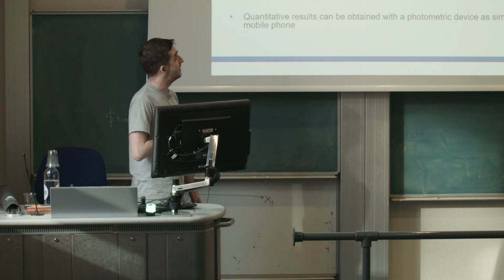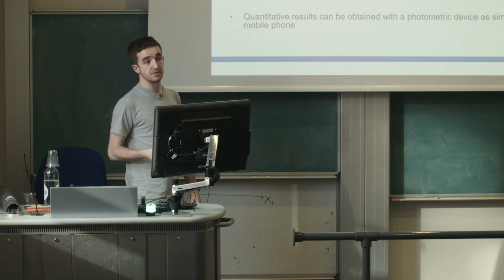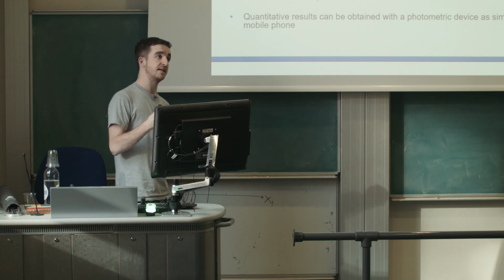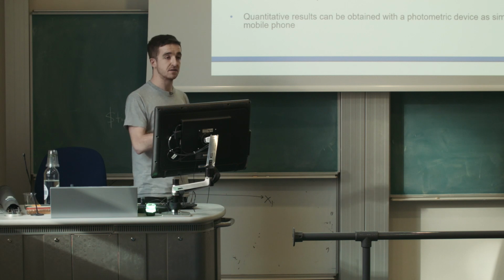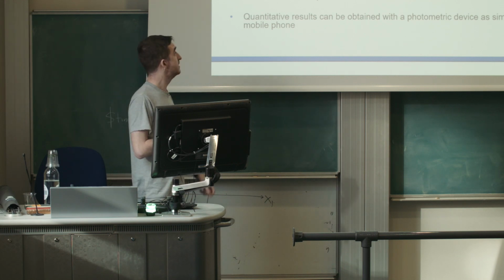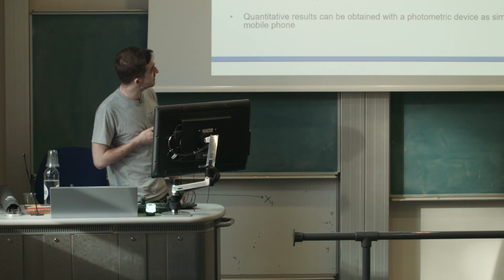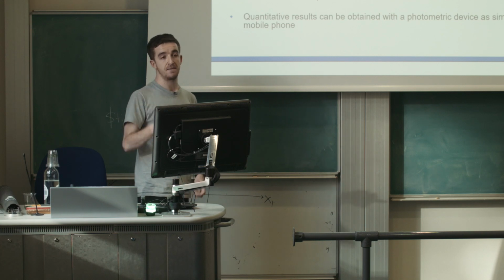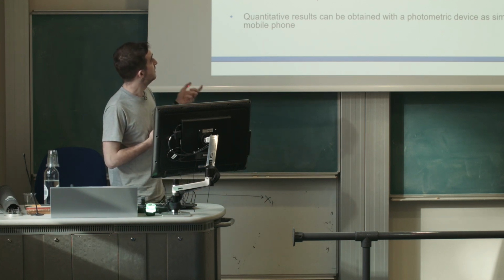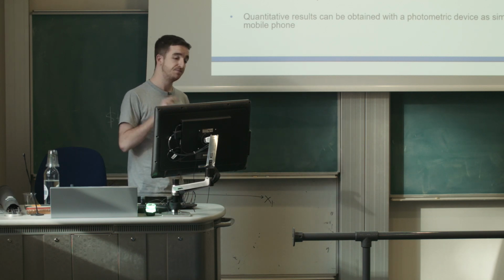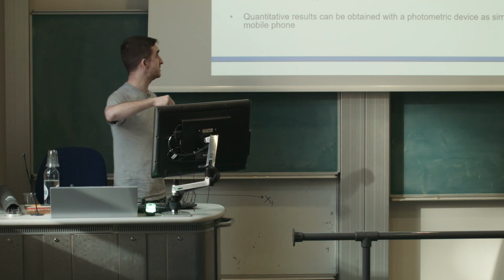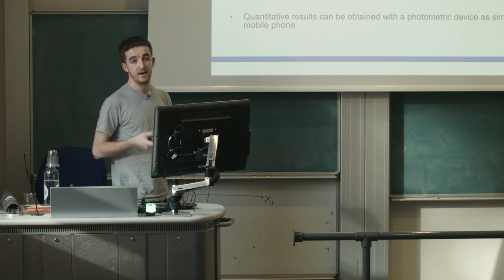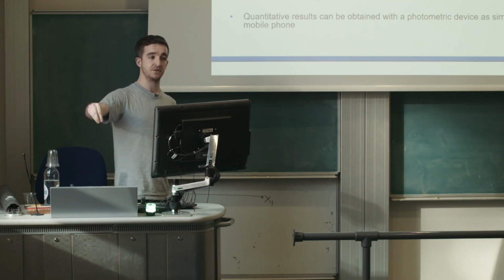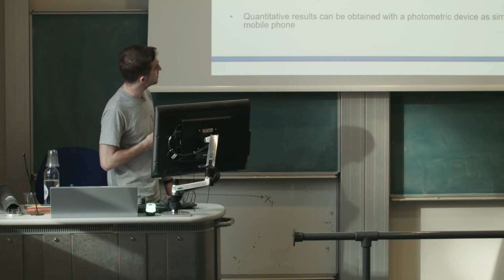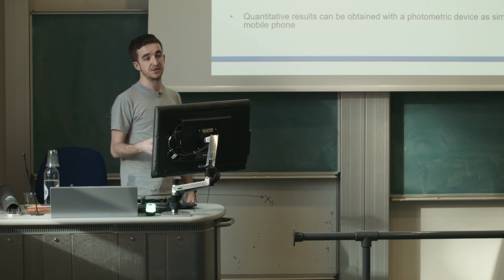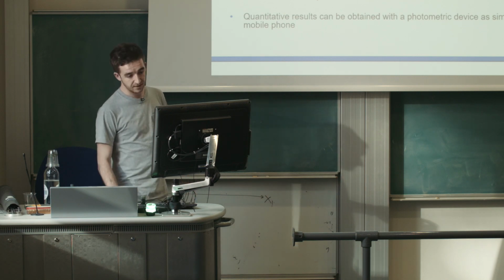So the reason these devices are better than the current technology is that they're entirely polymer, so they can go into MRI machines. They're real-time measurements because the sensing is inherently built into the polymer, so you don't have to worry about taking a sample, taking it to a lab, and then bringing it back to be able to get measurements of the patient's brain chemistry. Light is the only stimulant requirement, so that means that it doesn't require metal wires, which means that it doesn't interact with the MRI. The fiber is flexible and biocompatible, which means that you have less risk of inflammation and less risk of hemorrhaging from inserting the actual cable into the person's brain. There's no recalibration, as I'm sure a lot of you are aware. If you have electrochemical cells, you need to recalibrate by putting it back into a standard solution. These devices don't require that. And then also, the quantitative results can be measured using a photometric device, which is something as simple as the camera on your mobile phone, from the color of the wavelength that you get out.